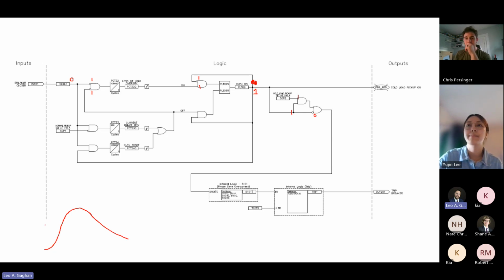So that 1.4 amps that we talked about, and let's say that was 1.9. Right, we didn't trip for that 1.9, we're happy. What happens here is it got up above that 1.4, and eventually it's going to fall back down and normalize where that 1.4 is maybe more appropriate. So cold load pickup is on. All right, we'll come down here. We've got a 1, right, because cold load pickup is on. And once it drops back down below that 1.4, right, we're going to have a 0. And we're going to have a 1.